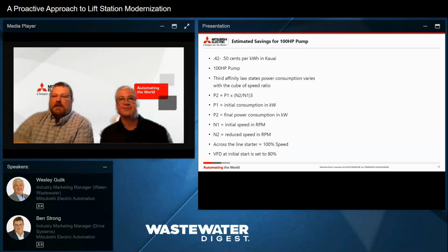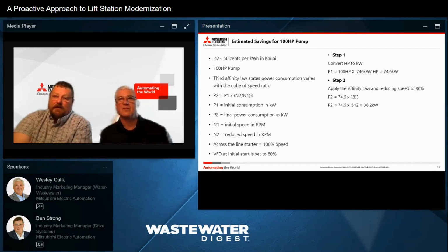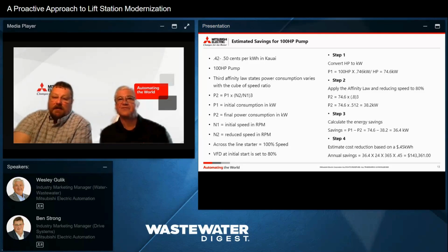So here is an estimate that was done for a customer in Hawaii. Their power is very expensive. I said the national average here is about 13 cents a kilowatt. On the islands, it's 42 to 50. So for a 100 horsepower pump using the pump affinity laws, we convert that to kilowatts. We reduce the speed to 80%, still keeping our frequency above the minimum speed for that pump. We calculate our energy savings, and then over the year, in Hawaii, they could expect $143,000. So if that pump were operating here in the continental U.S., the number would be closer to somewhere between 20 and 40, depending where you're at and how much that pump ran. So those are some pretty compelling numbers, depending on which input you put into these equations.